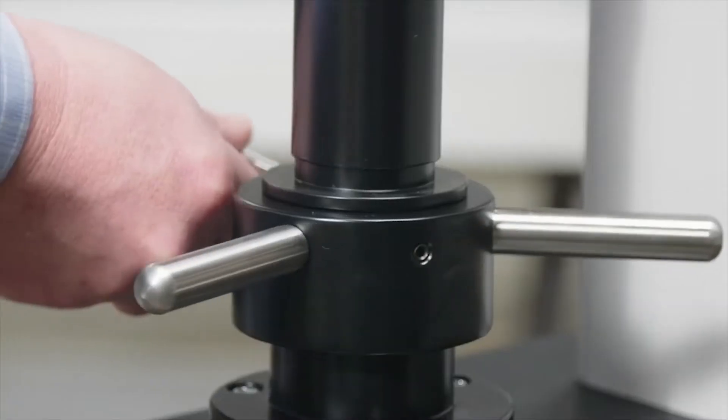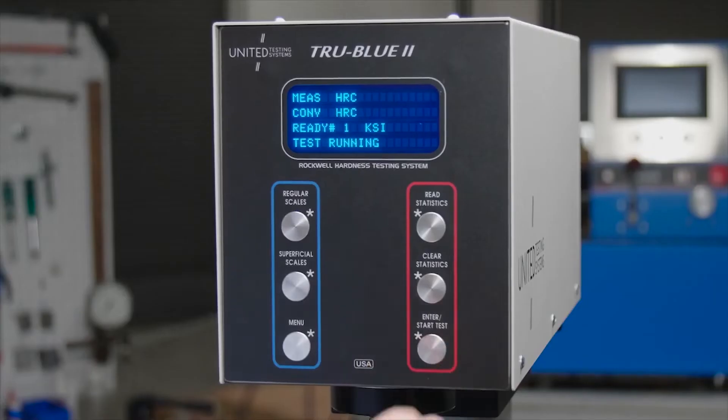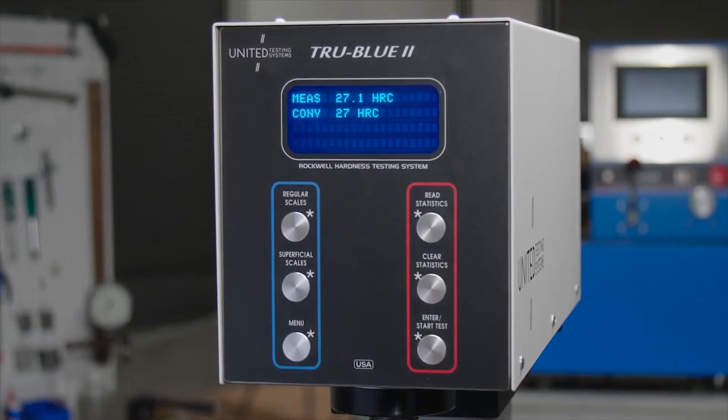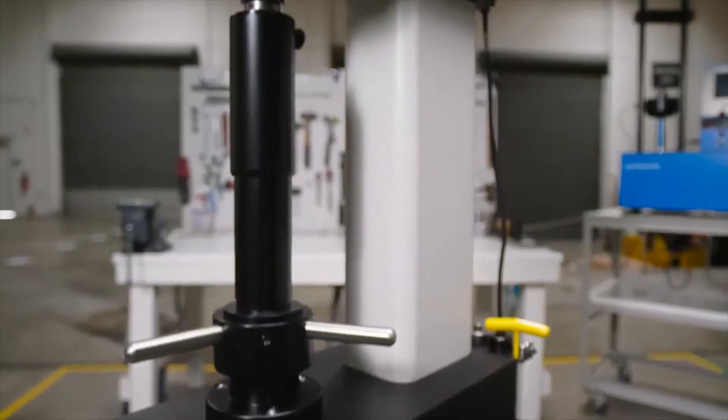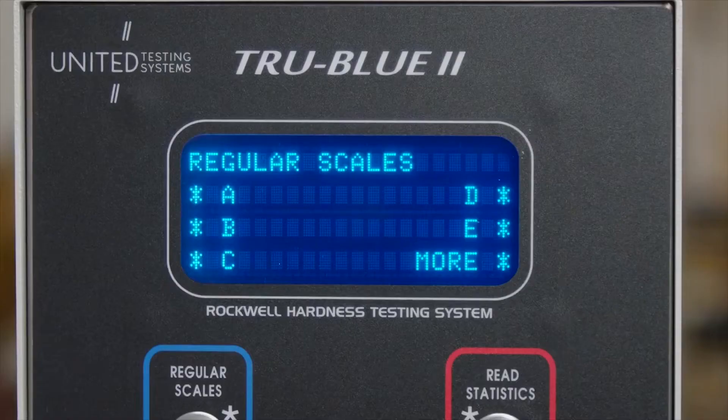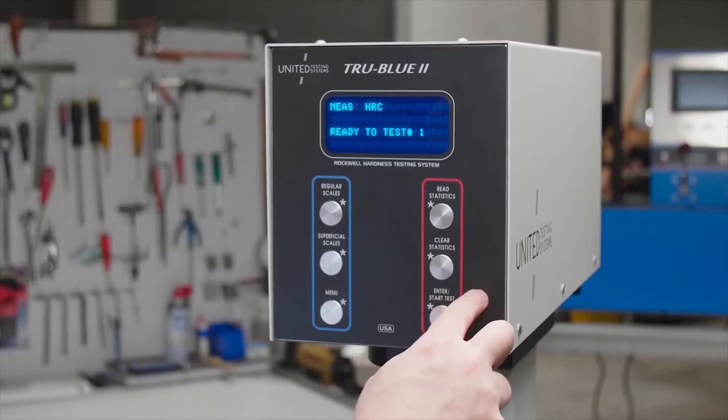Running a test is as simple as loading your sample and choosing a few test parameters. Tests can be run using the Start button located on the main panel or the secondary button on the side of the machine. Simple options make it easy to select regular scales or superficial scales as well as read or clear your statistics and change units of measurement.